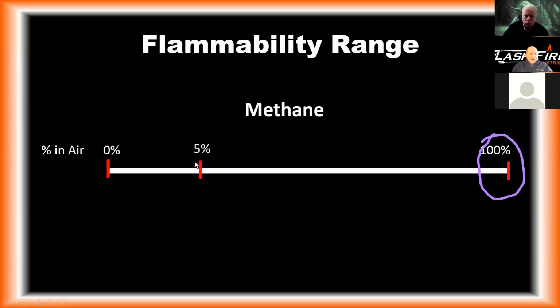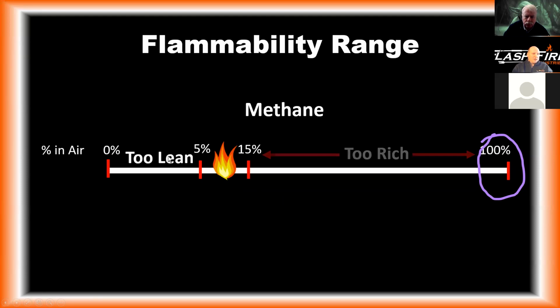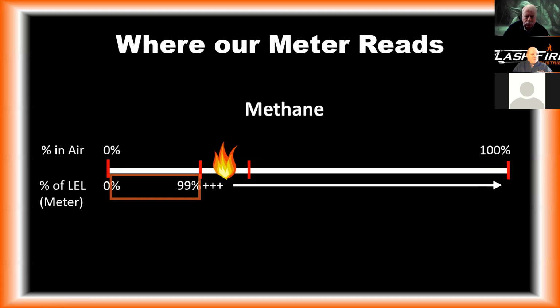If we're at 5%, that's our lower explosive limit. So in this area, we would be too lean. We don't have enough of the gas to burn. 15% is our upper explosive limit. So in this center area of air, if we have between 5 and 15% of methane in the air, we are in that explosive range. Less than that, too lean. More than that, too rich. All right. Are there any questions on that? This is one of those where it cascades. So if you don't understand the first slide, it only gets worse from there.